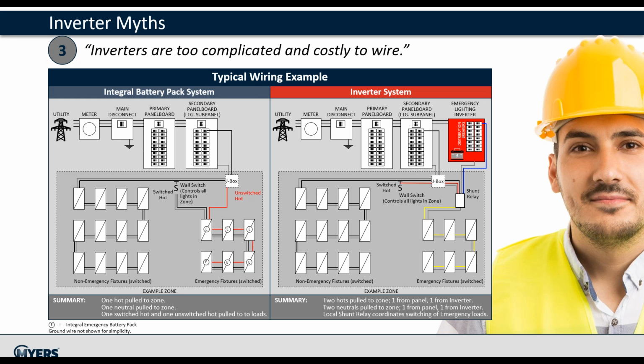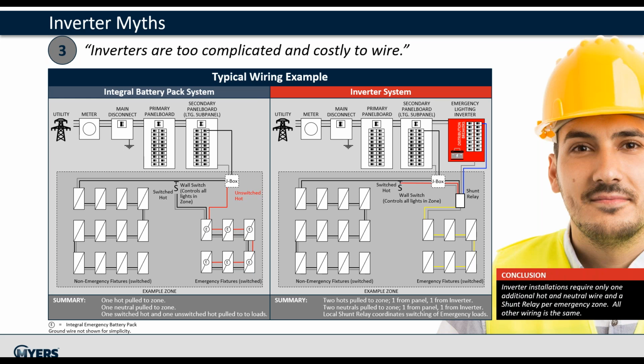In the case of inverter, downstream of the sub-panel, you have the input and output wiring to and from the inverter. A shunt relay is placed in each zone that the emergency circuit is wired through, and the switched-unswitched hot connects to the shunt relay as well. The shunt relay provides the sensing and control for the power to the emergency lights. The output of the relay contains the emergency wiring that powers the fixtures. In summary, the inverter system only requires an extra hot and neutral.